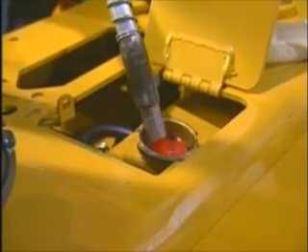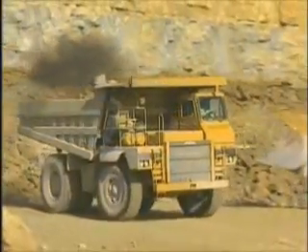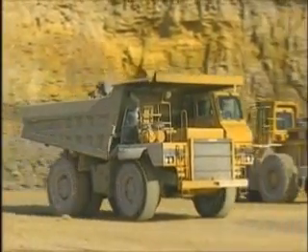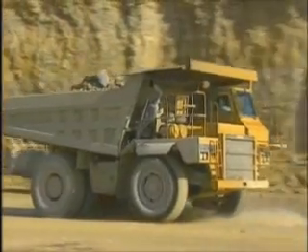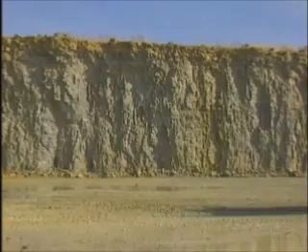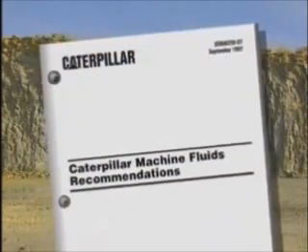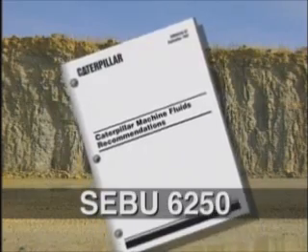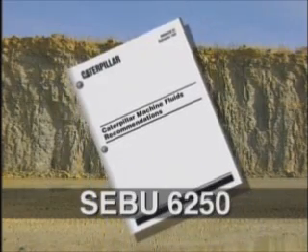CAT is demonstrating its commitment to the product by shipping all new machines with radiators full of ELC. The cooling systems already in your fleet can be converted easily to ELC. Just make sure you thoroughly flush all the conventional coolant and SCA before charging the system with ELC. The entire procedure is outlined in the Caterpillar Machine Fluid Recommendations Booklet, SEBU 6250.